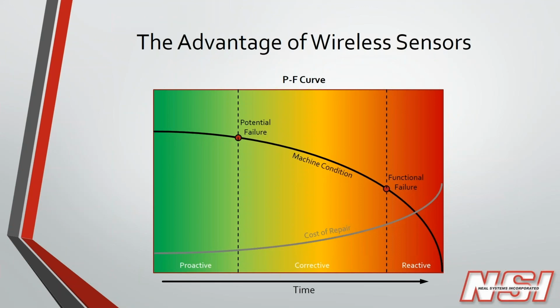But what is the advantage of a wireless sensor, right? If you're in maintenance, then this is a pretty familiar curve for you. It's called a PF curve, or potential failure to functional failure interval. When something changes, damage might occur to a machine, the condition starts degrading, and eventually you get to a point where the machine's not doing what it needs to do.